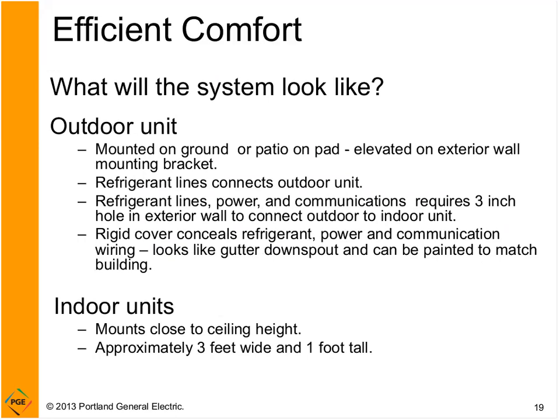So several options there. There are the refrigerant lines, which connect the indoor to outdoor units. The refrigerant lines, the power, and communications are all combined and require a 3-inch hole in the exterior of the wall to connect the indoor and outdoor unit. And then there's a rigid cover that really should be installed that conceals the refrigerant, power, and communication wiring. It basically looks like a gutter downspout and can be painted to match the building. So you really don't even notice that there is this system requiring this refrigerant line and cable and all this.